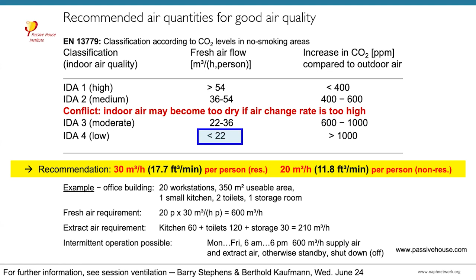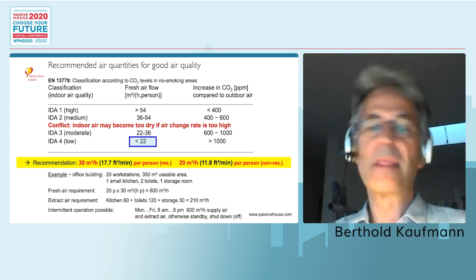If you take in dry and very cold air and heat it up, it may get even lower relative humidity, and therefore the recommendation is for a residential home 30 cubic meters per hour or about 18 CFM. And for non-residential use, so office building or classrooms or meeting rooms, down to 20 cubic meters per hour or about 12 CFM is quite enough. So we know this is a compromise, but we think it's a good compromise to not go to too dry air during winter time.